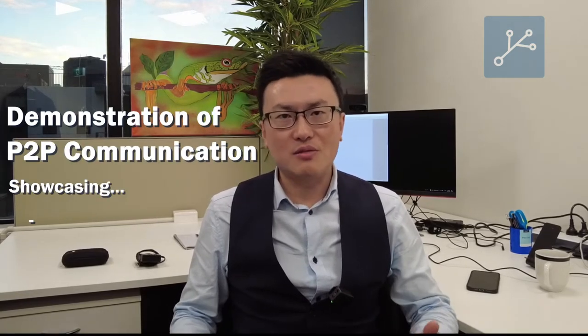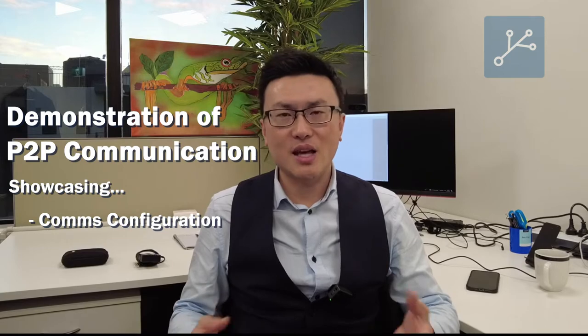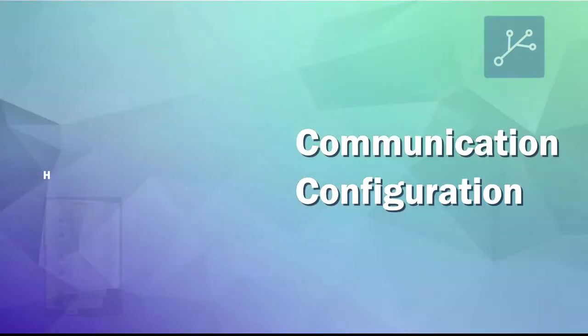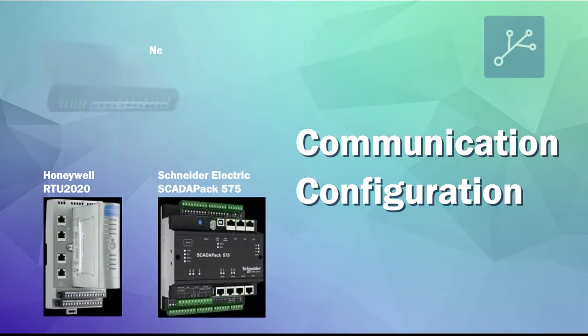Our engineer Finn is going to give us more details about the configuration he's created and the testing he's done so far. This is the communication between the RTU 2020 from Honeywell and the SCADA Pack 575 RTU from Schneider. Currently we have the SCADA Pack set up as the master and the RTU from Honeywell set up as the slave.